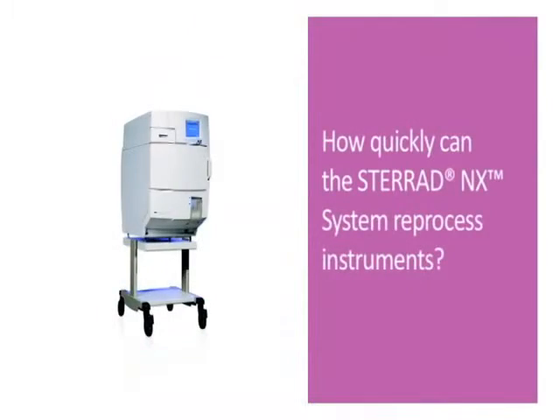The next question is, how quickly can the STERRAD NX system reprocess instruments? The bottom line is that the STERRAD NX system is a great fit for the OR environment because it offers terminal sterilization. With its 28-minute cycle for most standard instruments and 38-minute cycle for single-channel flexible endoscope, it most closely resembles the time used with the STERIS System 1.